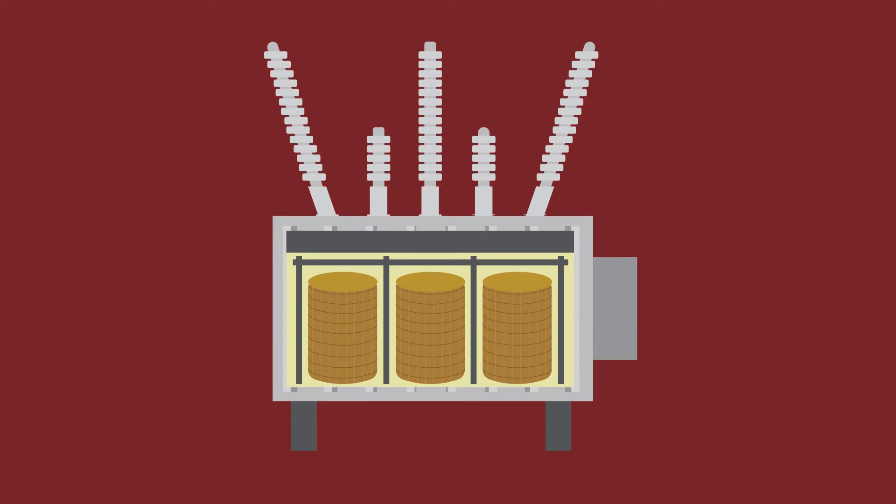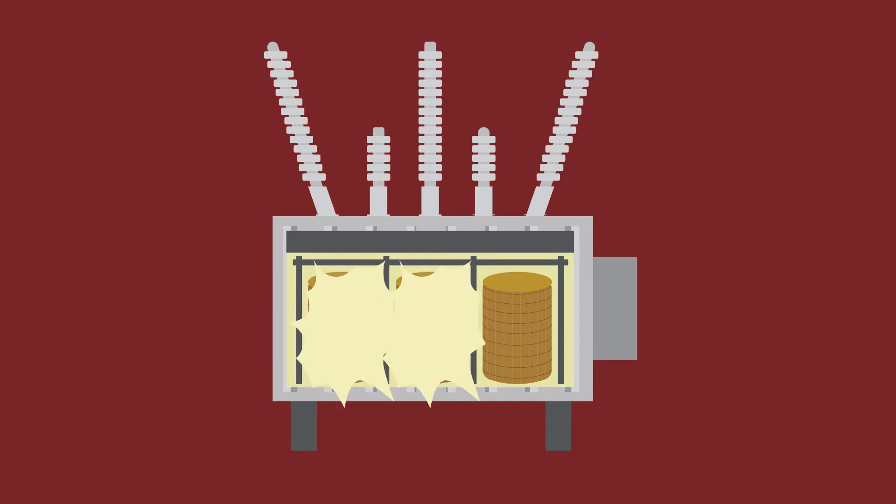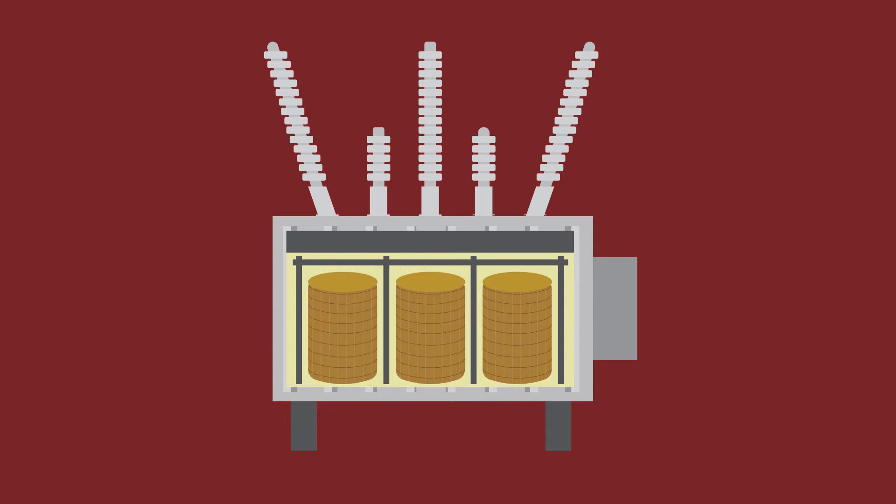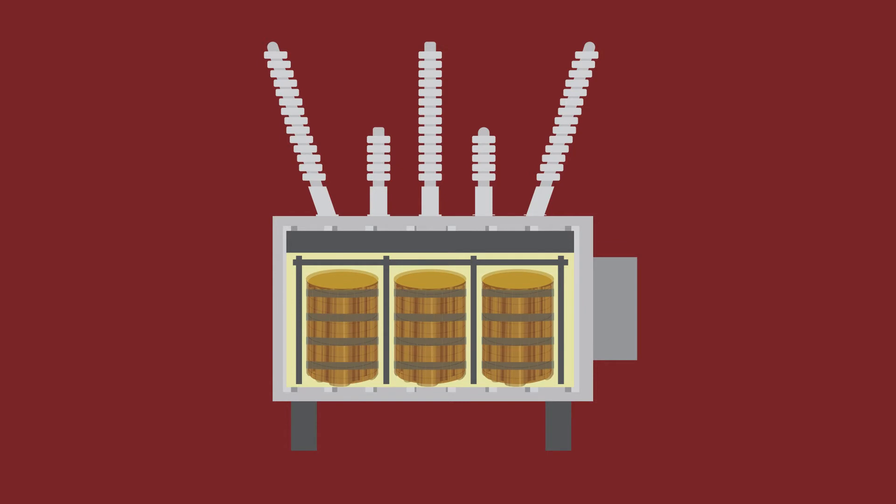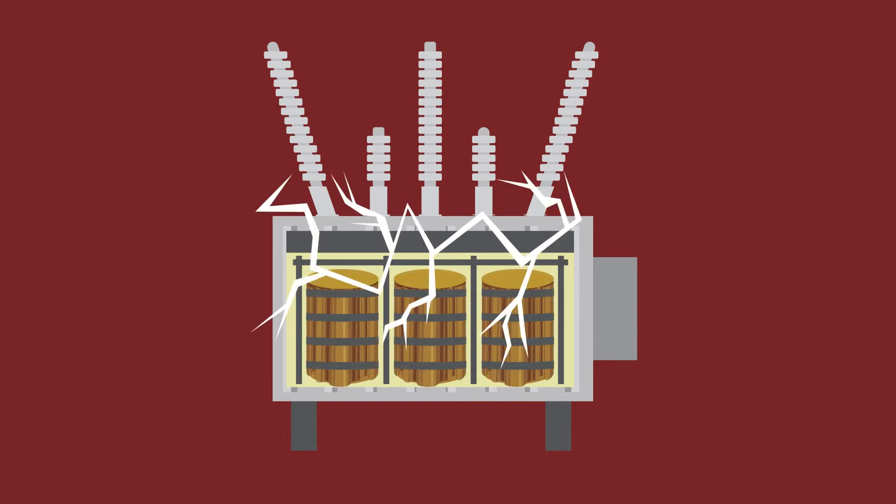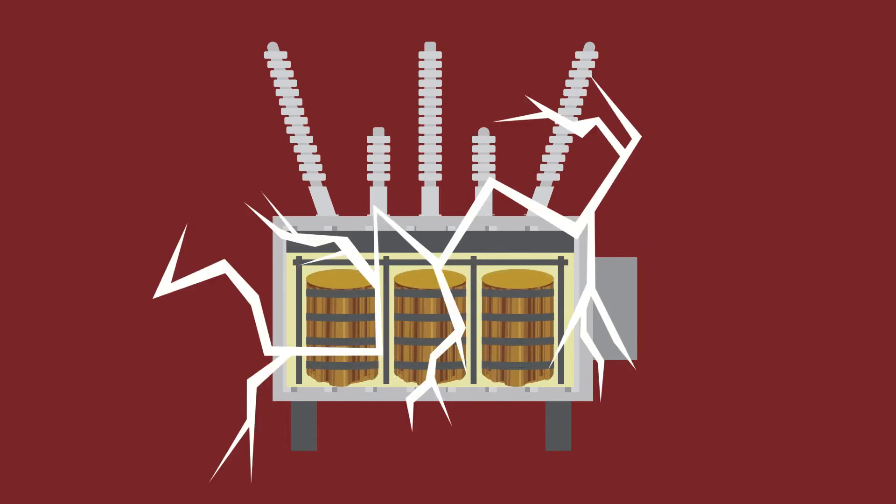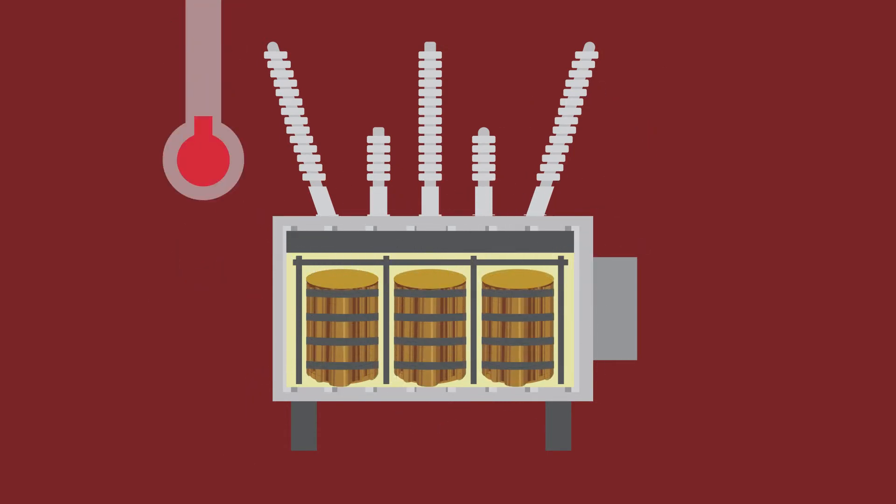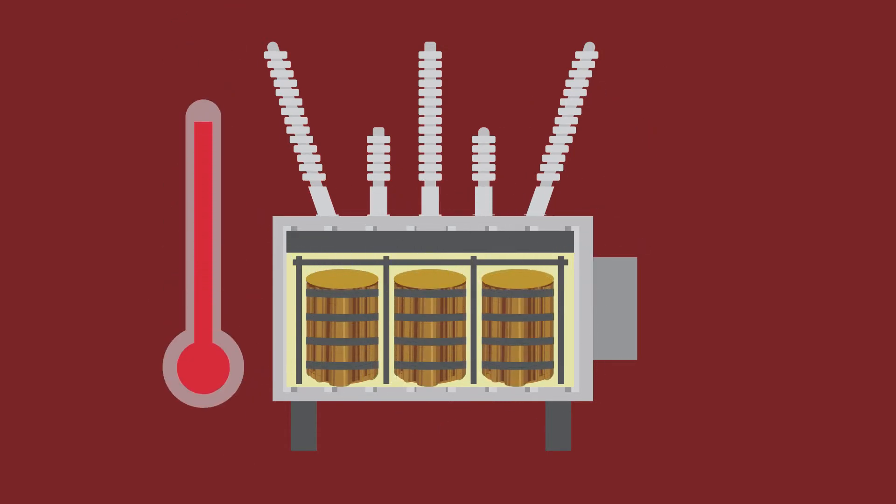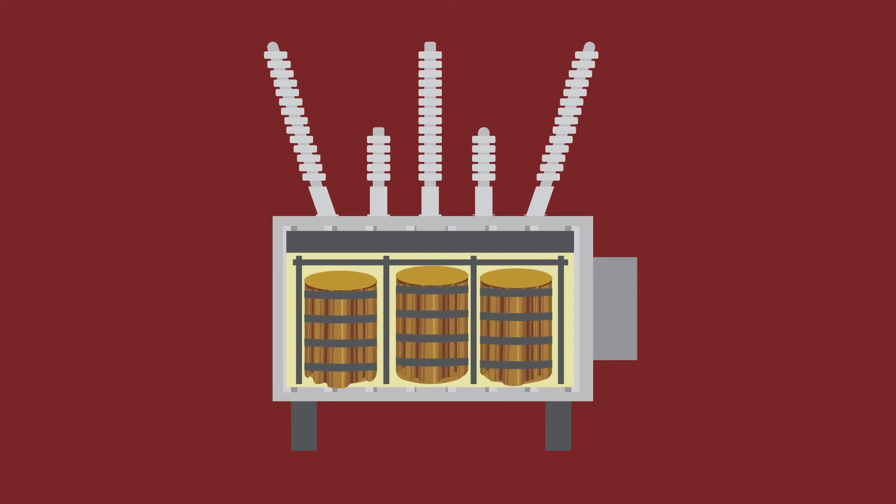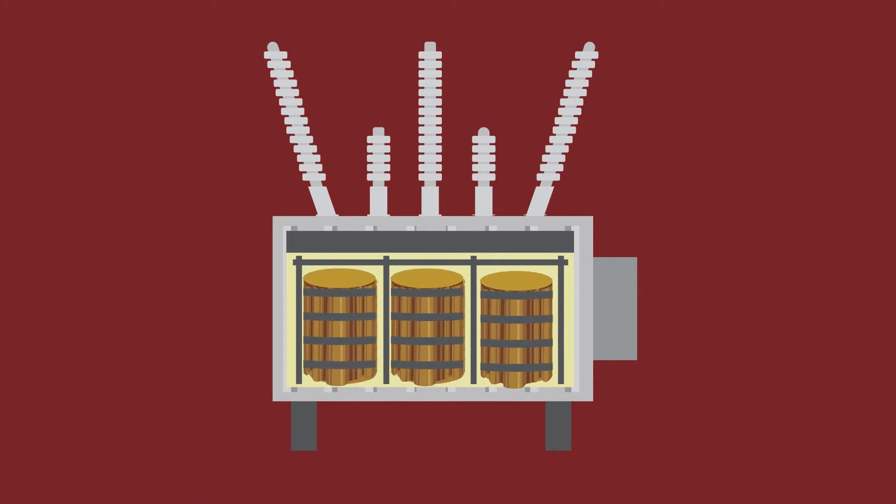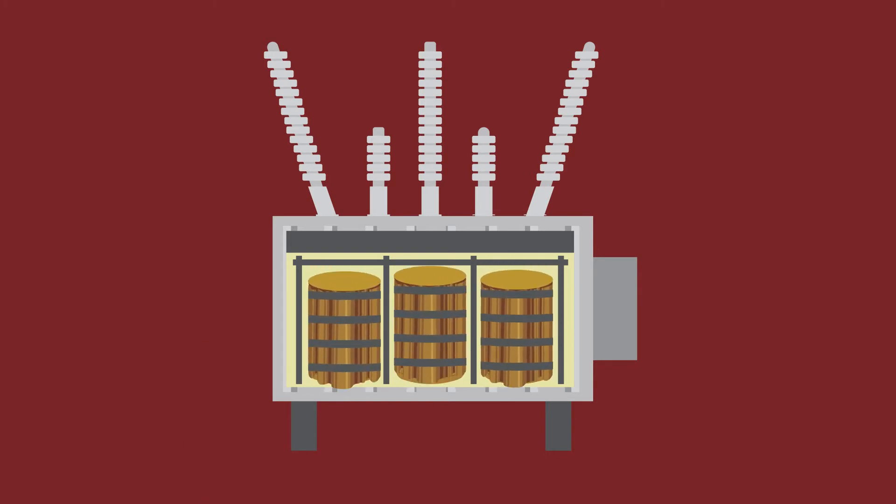Distortion or buckling of the windings contributes to multiple modes of transformer failure. Turn-to-turn, winding-to-winding and winding-to-ground shorts, breakdown of insulating materials, partial discharge, arcing, and disruption in cooling channels are examples of complications resulting from the movement of the winding.